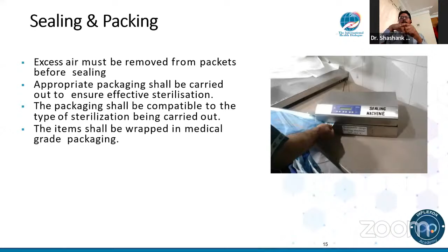Second, if you are planning to do double packaging for sterilizing, you should always ensure that there is no inner folding. This is a very common mistake. Whenever you're doing any kind of packaging, especially since most of these are ETO packing, in ETO the inner packing's plastic side should face the plastic side, and the paper side should face the paper side. This is commonly mistaken, and using a good sealing machine becomes very important. A 4-layer or 3-layer sealing would definitely be a lot safer and better for the patients, to withstand the packaging.